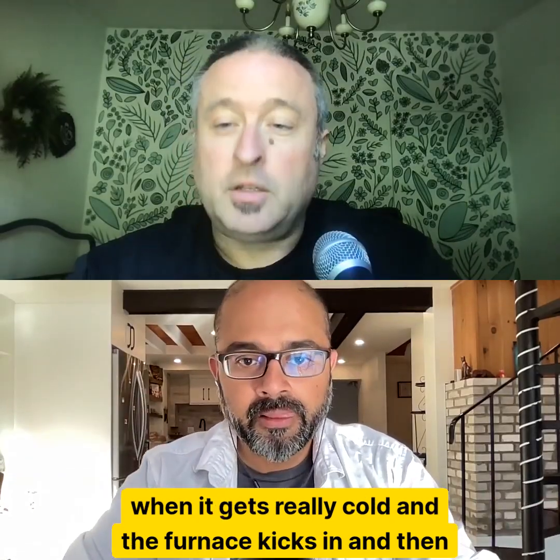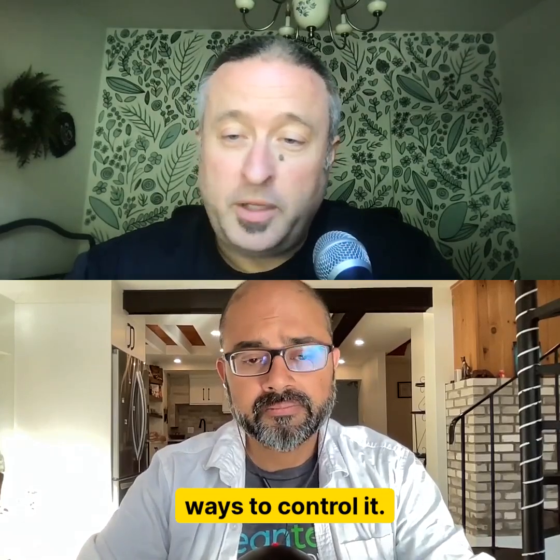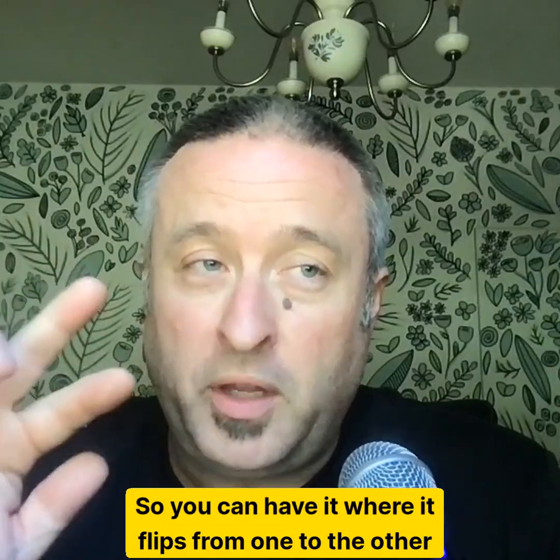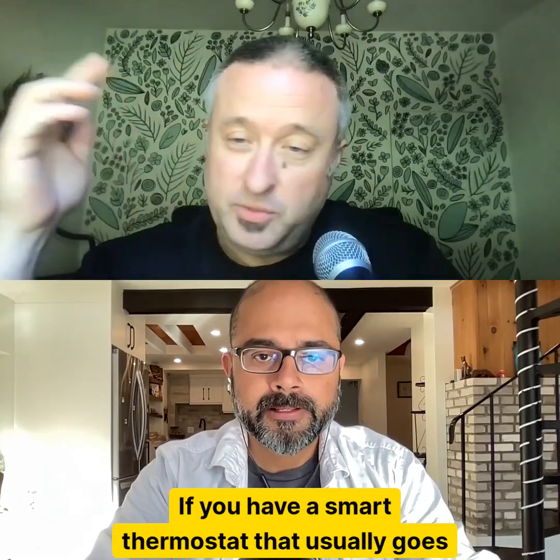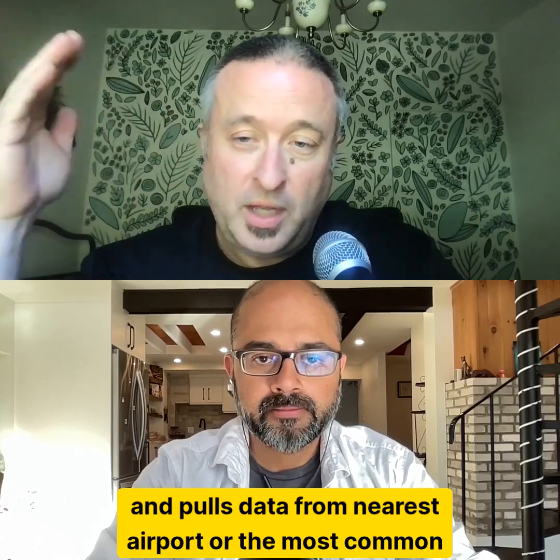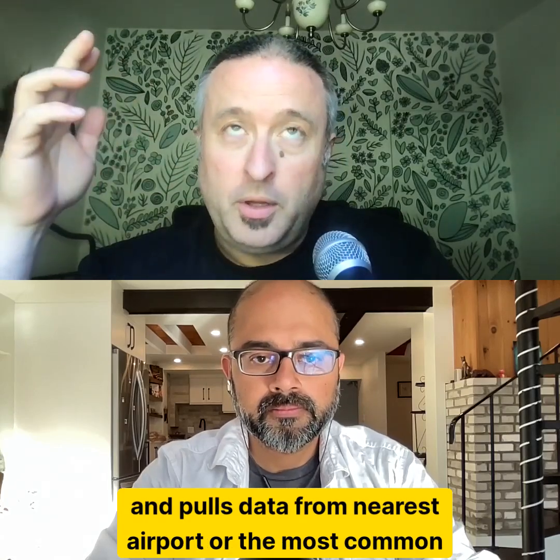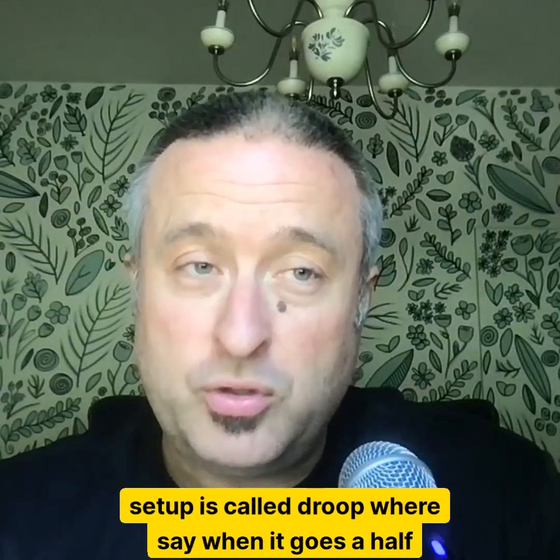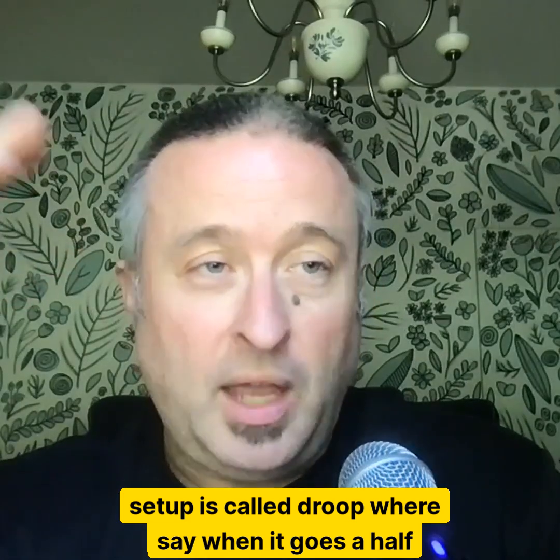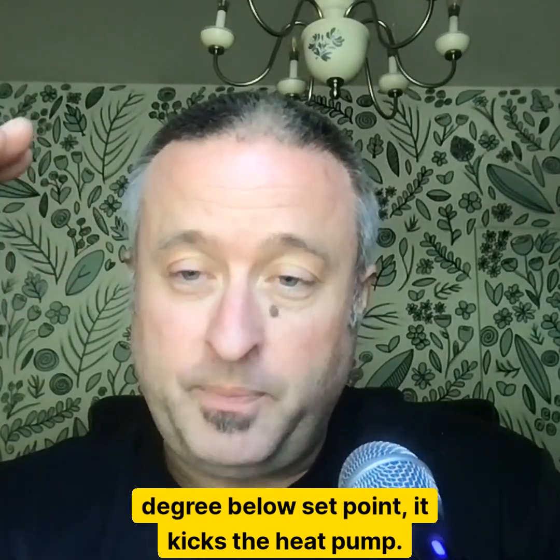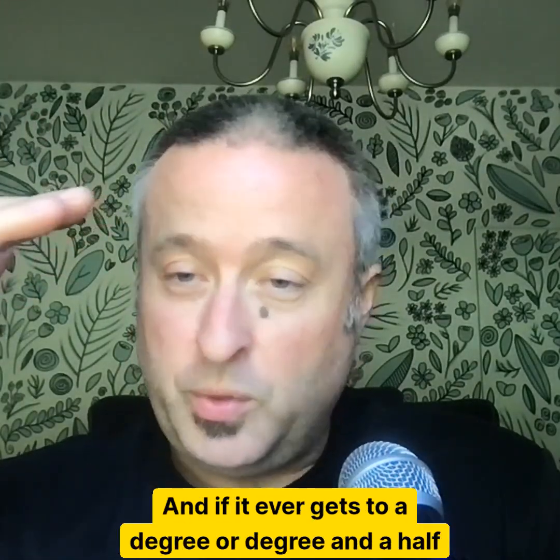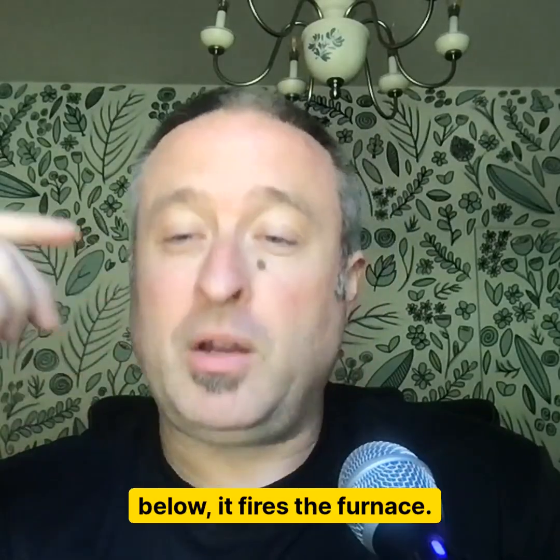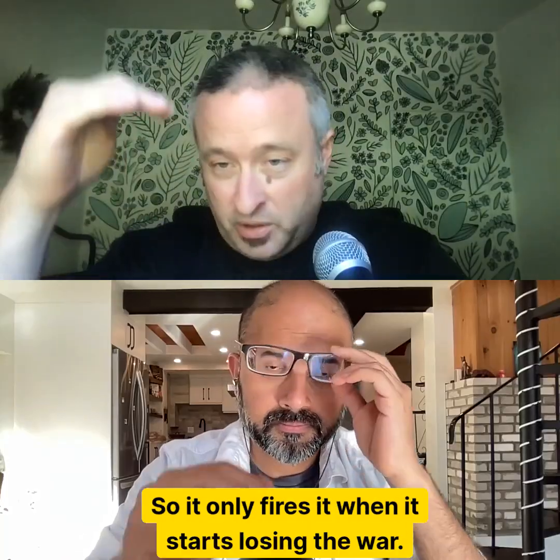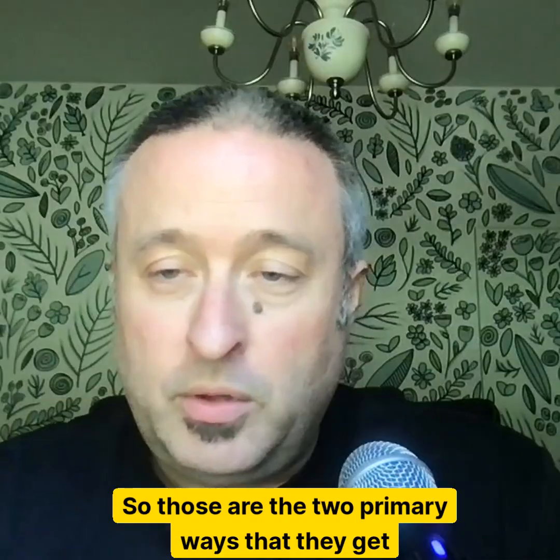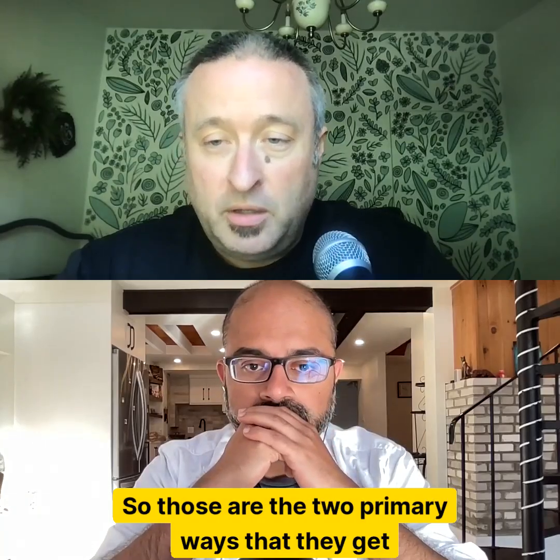Exactly. Yeah. There are a couple of different ways to control it. You can have it flip from one to the other at a certain outdoor temperature. If you have a smart thermostat, it usually pulls data from the nearest airport. Or the most common setup is called droop, where when it goes a half degree below set point, it kicks on the heat pump. And if it ever gets to a degree or a degree and a half below, it fires the furnace. So it only fires it when it starts losing the war. So that's the droop method. Yeah. Those are the two primary ways that they get controlled.